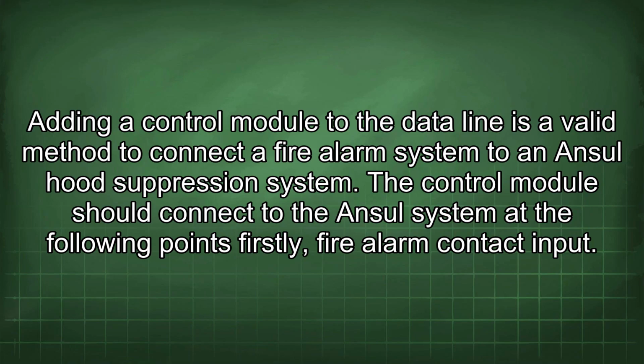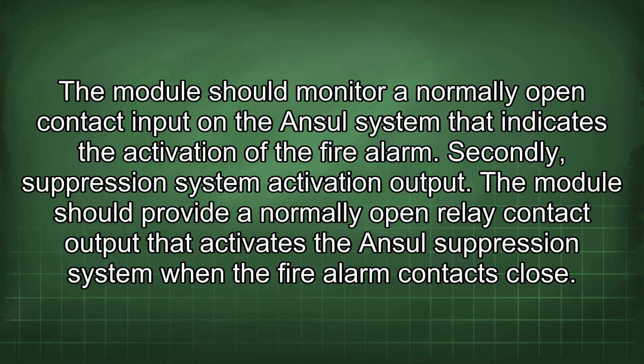Adding a control module to the data line is a valid method to connect a fire alarm system to an Ansul hood suppression system. The control module should connect to the Ansul system at the following points. Firstly, fire alarm contact input. The module should monitor a normally open contact input on the Ansul system that indicates the activation of the fire alarm. Secondly, suppression system activation output.